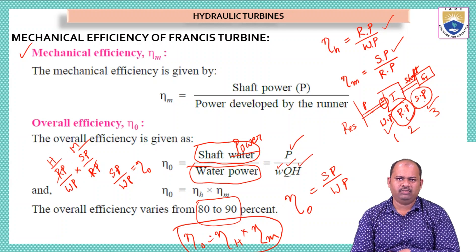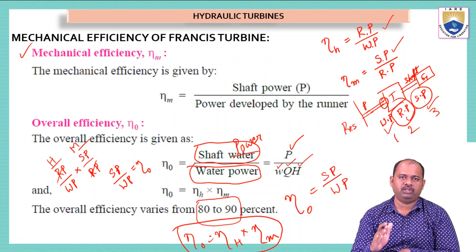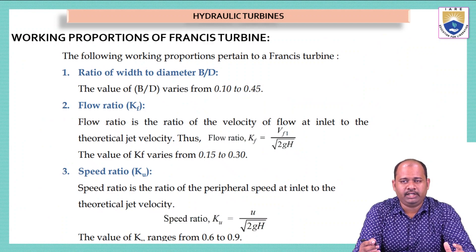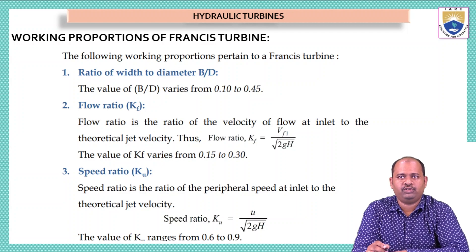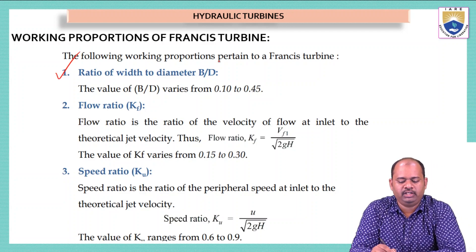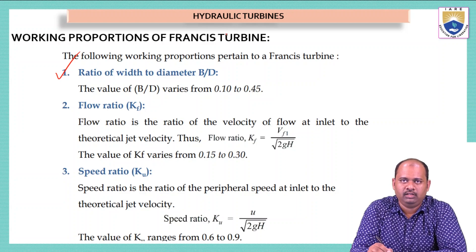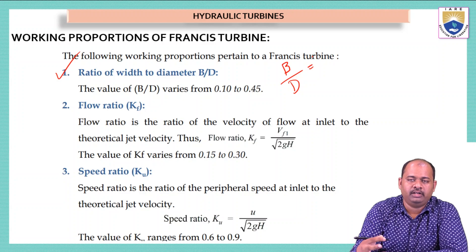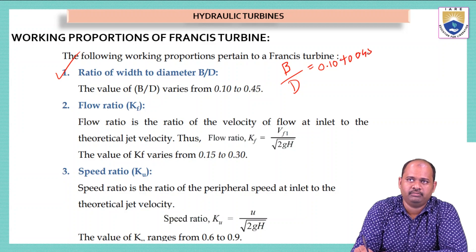This relation is not only valid for Francis turbine but for any hydraulic turbine: overall efficiency is the product of mechanical and hydraulic efficiencies. Now we will see some formulas related to the Francis turbine — the working proportions. First is the ratio of width to diameter (B/D), which stays between 0.10 to 0.45. This ratio is directly related to the diameter of the runner and the width of the spiral case or vane.